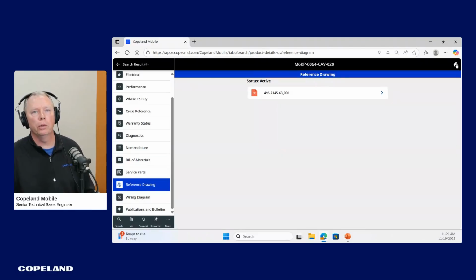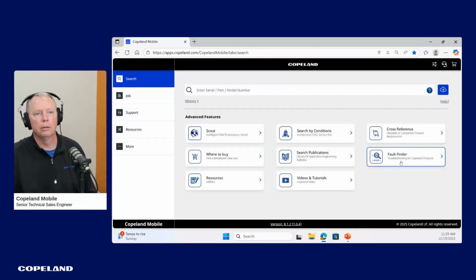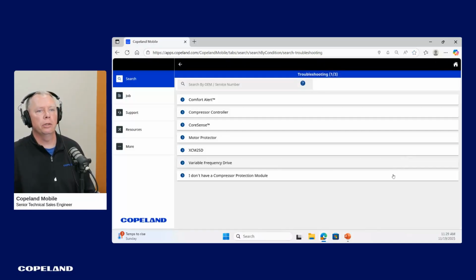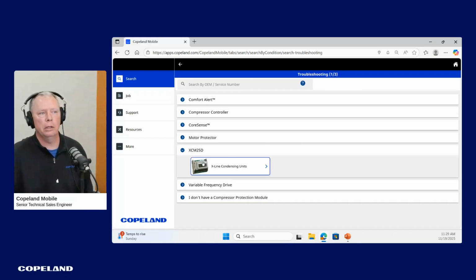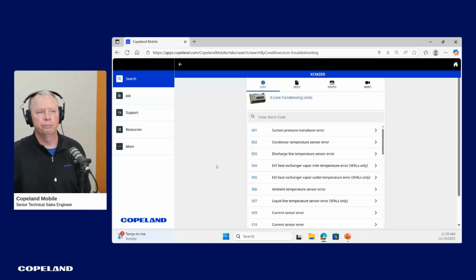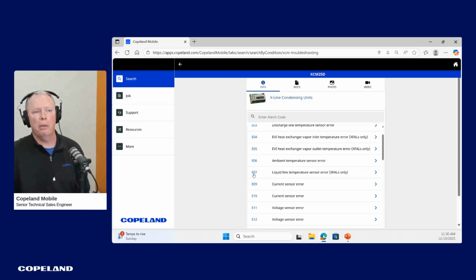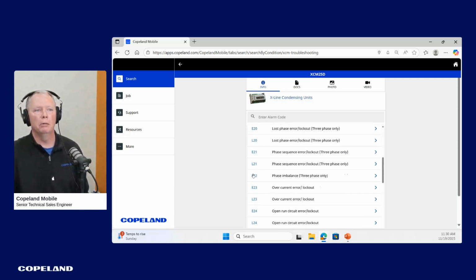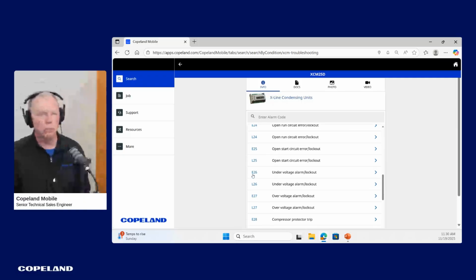Another feature we're going to move on to in the app that's very helpful is fault finder. We'll touch on this one briefly. As you can see, what populates when you go to fault finder is the different compressor and condensing unit modules applied today. For this example, we're going to use the XCM25D, and it actually shows you a picture of it. This is the controller of the Copeland X-Line units. So if you're on a job site with an X-Line unit giving you a code, you can choose this option and go through to see each of the codes displayed on the controller and the definition behind it. It'll give you some direction on what you're seeing so you can troubleshoot a little more quickly.